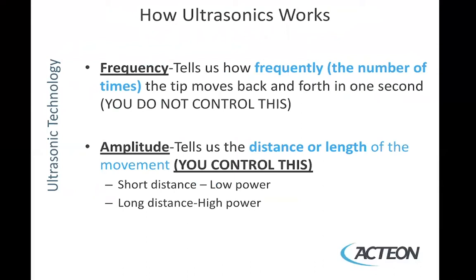How does ultrasonics work? There are two basic features: frequency and amplitude. The frequency tells us how many times the tip moves back and forth in one second — this is controlled by the circuitry, not by you. What you can control is the amplitude, which tells us the distance or length of the movement. A shorter distance is low power; a longer distance is high power.